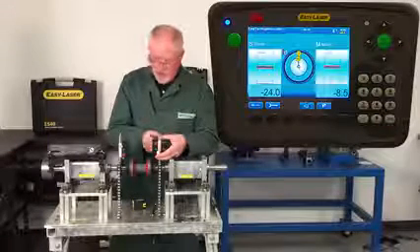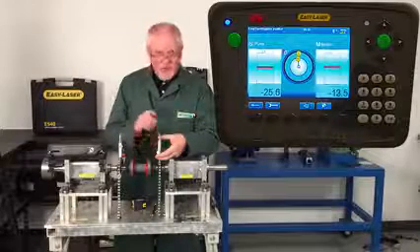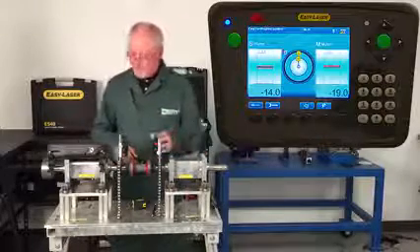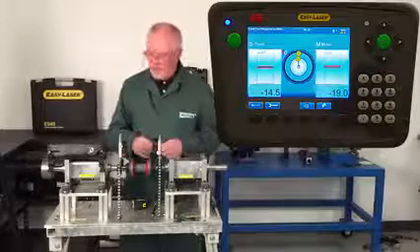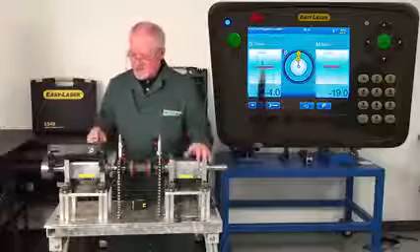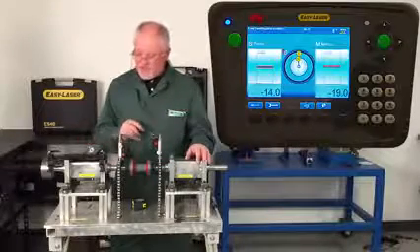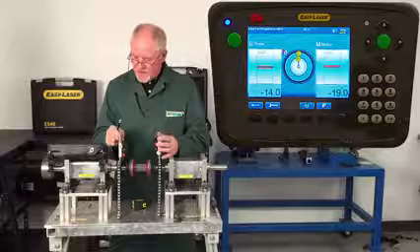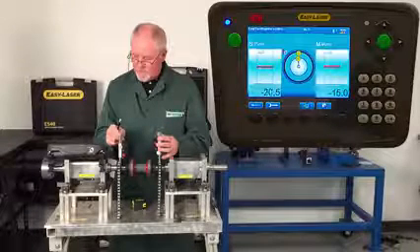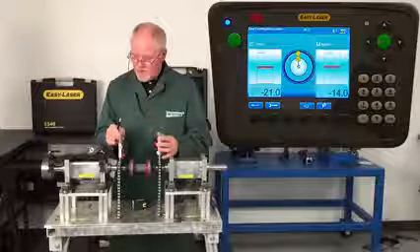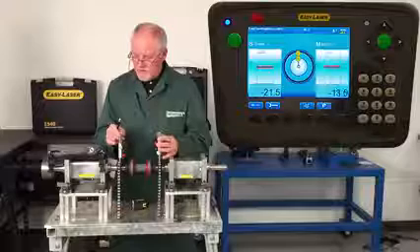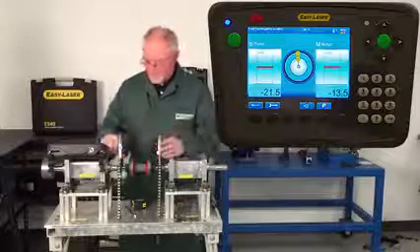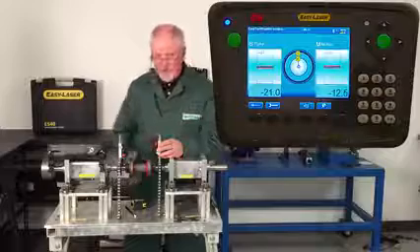Now when you look at the detector surface, what I'm trying to do is I'm trying to get this to be in the center of its travel. And that's roughly there. Now I'd actually be happy with that because I'm under the 20 thou. I don't need to move it any more than that. The other thing that's important to me though is this. These are built-in inclinometers, and we have one on each head, and they have to be within a degree. In other words, opposite each other in this plane here. So in order to make them so, I have to just move the unit. And that's going to be close enough. Now simply tighten them up.